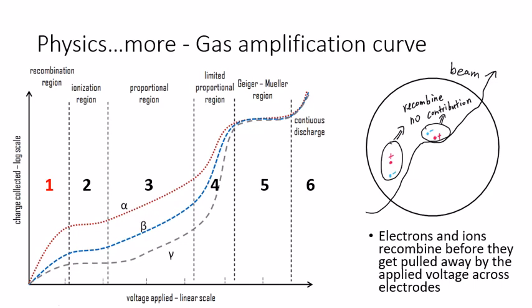This is essentially what happens in region 1, and we call this region the recombination region. The recombination region is no use for clinical dose measurement because of its instability.